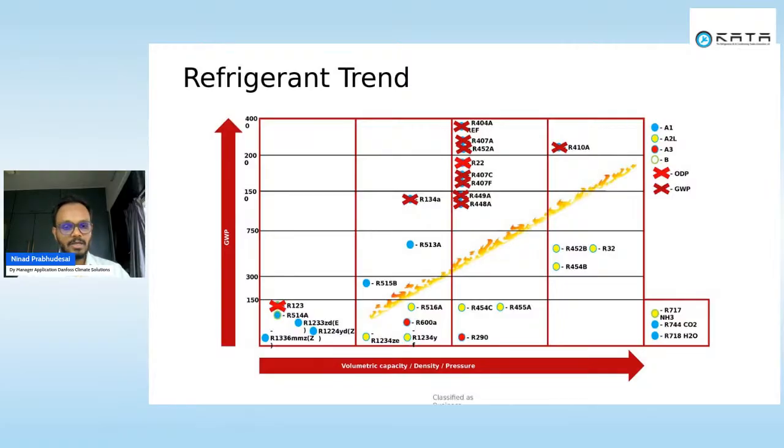And for very high temperature heat pumps, above 140 or 145 degrees, I think they are going for R1336MZZ and also R245FA. Of course, these gases have their own challenges in the system. They are certainly not always drop-in replacements where I simply remove the R134A and put in R600A or R1234ZD. It's not always like that.